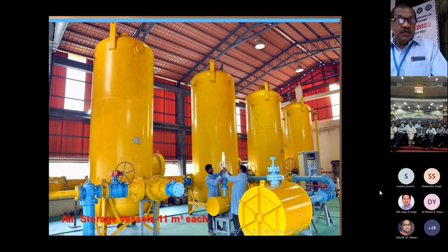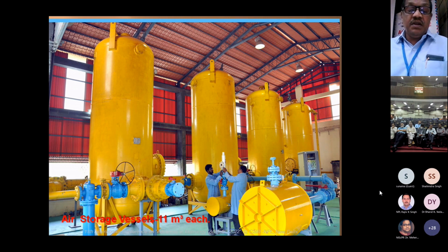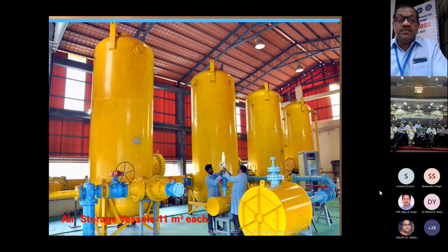Then this conditioned air is stored in four vessels. Each vessel has a capacity of 11 meter cube. All four vessels are interconnected through a 12-inch manifold with individual isolation valves, so we can take any combination depending upon the requirement. This setup we also use for testing of safety valves, basically discharge capacity. Earlier, capacity determination was not done, but nowadays, other than the set pressure certification, capacity certification at the design stage is also mandatory. So to some extent, we use this facility for testing of safety relief valves.